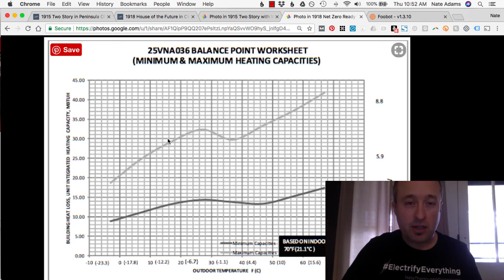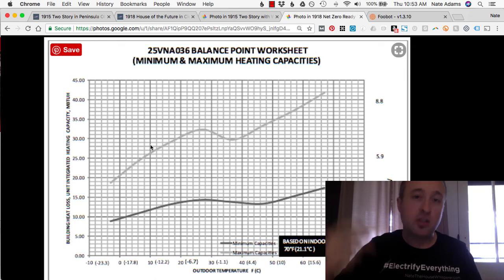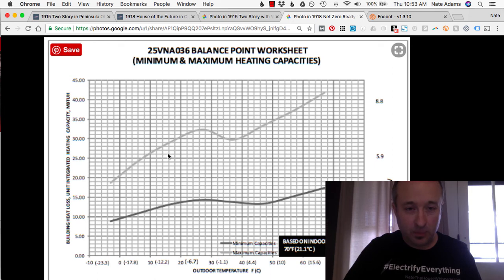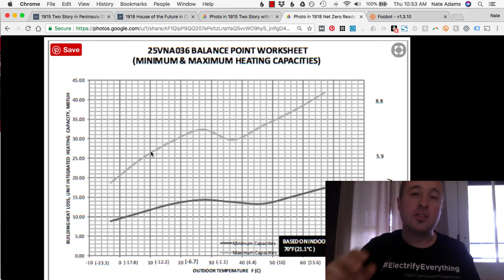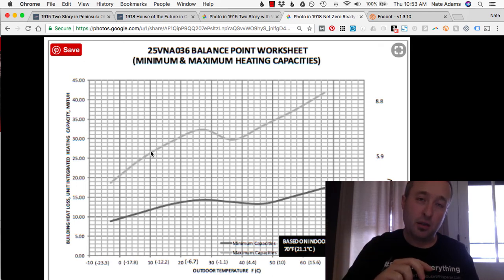This shows how much heat that unit puts out at various outdoor temperatures. I know from John's house that it starts losing the war somewhere around 10 degrees. At night it'll lose the war at 12 or 14 degrees, during the day not till about 5, because the sun helps quite a bit with heating the house. But if around 10 degrees it loses the war, I look at the output of the heat pump, and it's about 26 or 27,000 BTUs, so we're right in this range, which basically verifies the load calculation for this house.